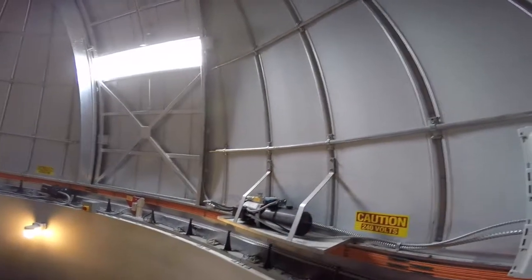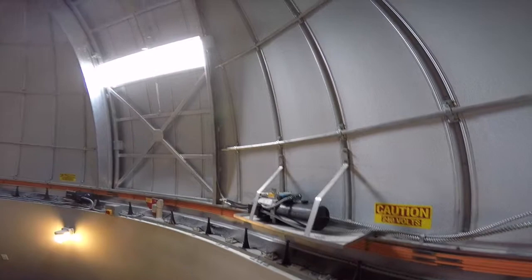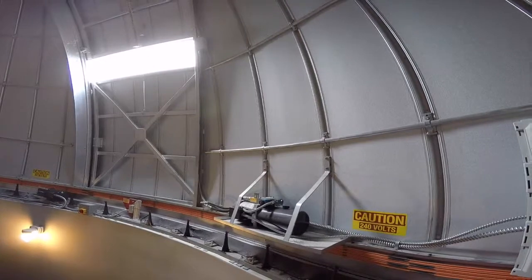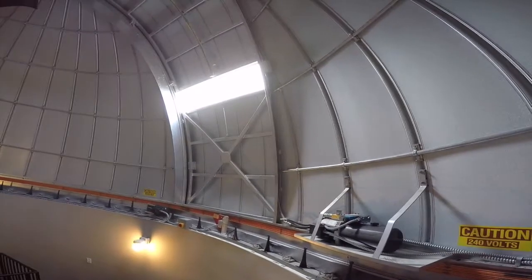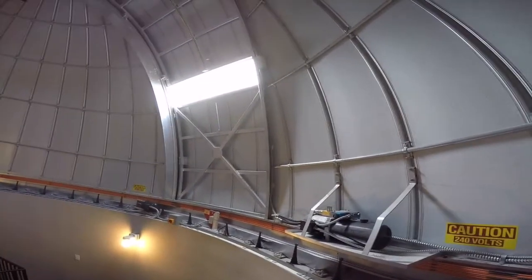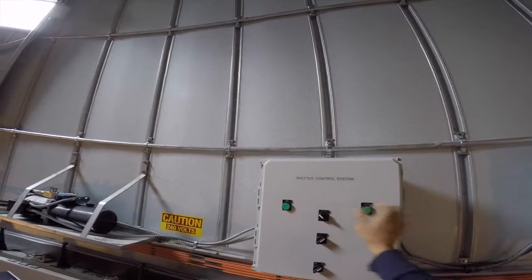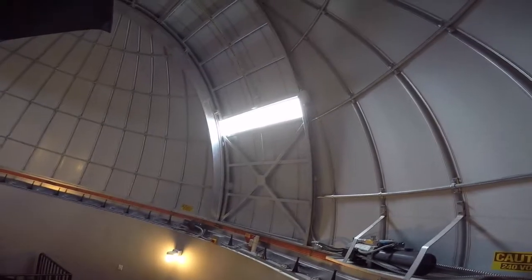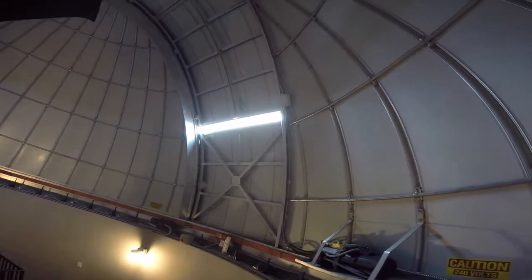This unit right here is the hydraulics for opening the lower shutter. It also has a bypass valve, so if anything happened and the proximity switch didn't cut the motor right away, the bypass valve would kick in, and you're not going to get an overpressure situation where hydraulics are continuing to try to open or close the shutter when it can't be either opened or closed. Let's go ahead and go back to upper and then close. And when it gets fully closed, again, the limit switches will cut things off.